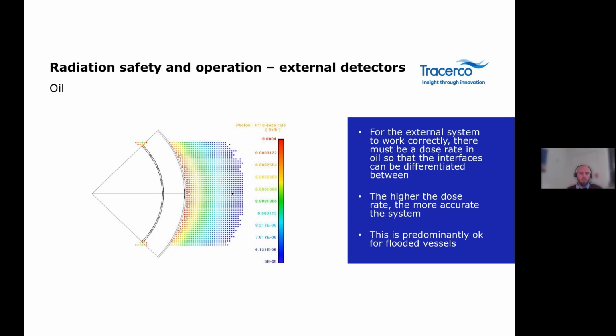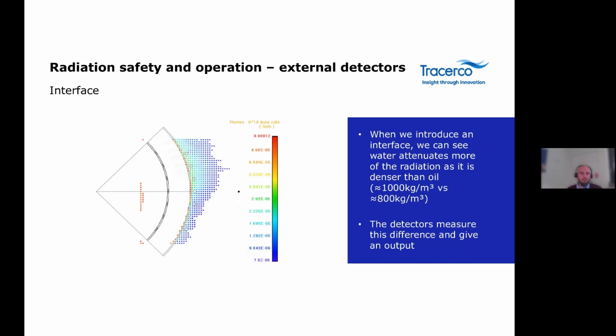But generally speaking, this is okay for flooded vessels where the process attenuates some of the radiation, reducing that dose rate. When the external system is able to measure the interface level using this attenuation in radiation, where there is water in the vessel, the count rate is shown to decrease, showing an increase in density. The detectors observe this difference and will give the output based on the calibration set points of the fluids.